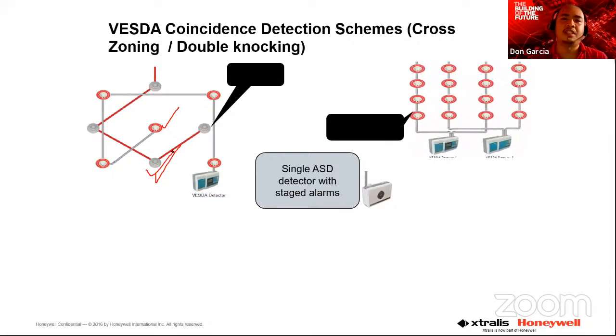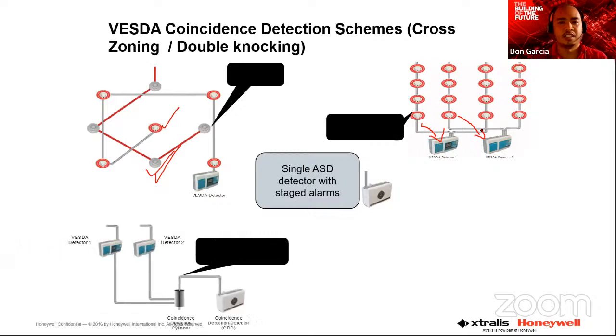Second scenario is they use two ASD detectors, meaning your two ASD detectors are cross-zoned. You're using pipe monitoring of smoke from the first stage ASD detector and you will use the second stage for the next ASD detector. So you can be sure there's no false alarm because automatically it only reads smoke. Even if it could detect dust, there are filter stages inside the ASD detector so dust cannot penetrate going to the smoke chamber of the ASD detector.